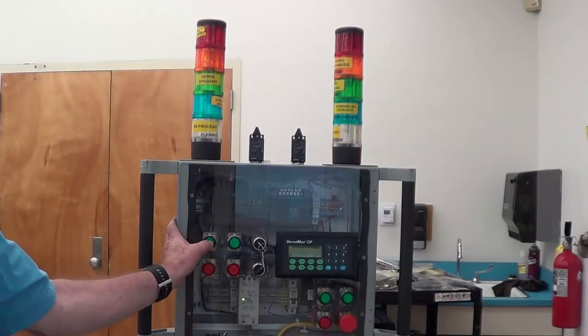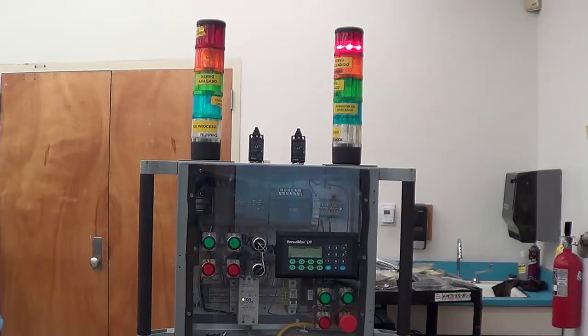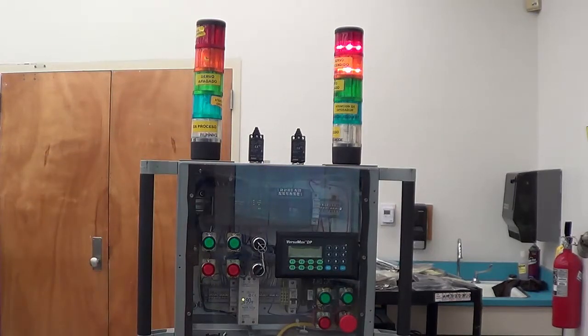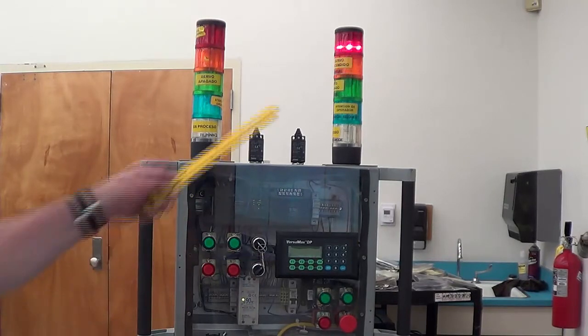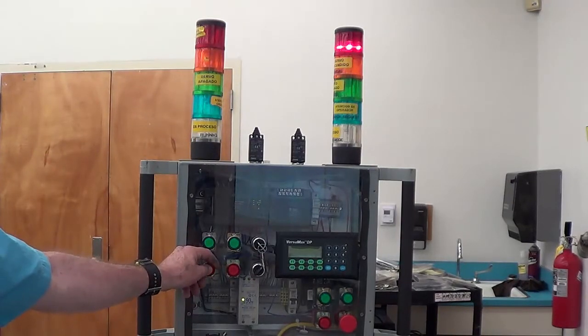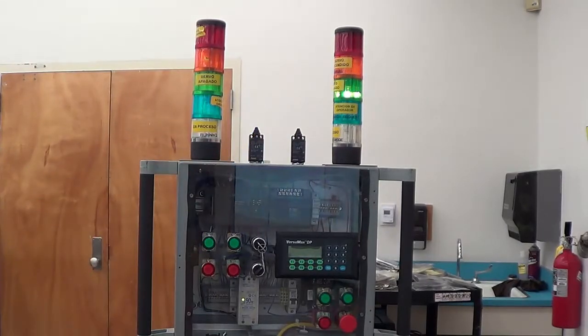So push the start. Motor 1 is running. We're in our first delay period. We're up to 50 seconds in it. Okay, 90. There we go. There's our output number 1. It's on, so we're in the second delay period now for that to be on. 70, 90, and then it's off. Now we're running. Hit the stop button. Motor stops. Output number 2 comes on. It'll be on for 10 seconds. We're good to go.